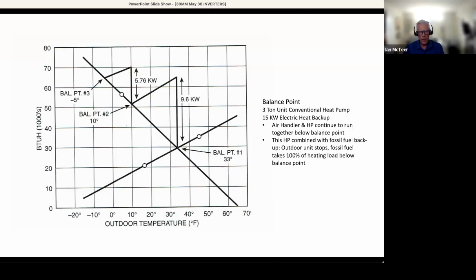So you can see that that third balance point is beyond the outside design temperature. So there's a bit of a fudge factor in there for the times that the temperature does get a little bit lower than the calculation. So, all in all, as Gerry said, these cold climate vapor injected heat pumps are truly a tremendous innovation in the industry. And the sooner we can get more of them out there, the better.